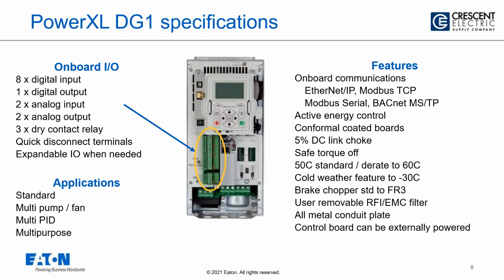All of our boards are conformal coated, and that's not only this one, but also the DM1, which just does wonders from an environment standpoint. This one has a 5% DC link choke built into it. It also has a safe torque off built into it. It's a SIL category 1. It has a very high temperature rating. We can derate this up to 60 degrees C, so that's something that's kind of unusual in this frame or this class of drive. We do have a cold weather feature.